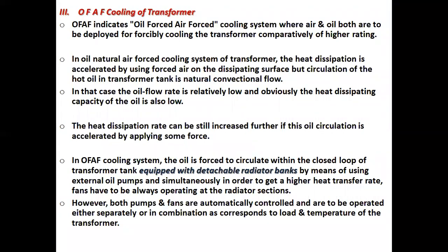Now, number 3 cooling arrangement, that is OF-AF type cooling of transformer. OF means oil forced and AF means air forced cooling system, where air and oil both are deployed for forcibly cooling the transformer of comparatively higher rating.